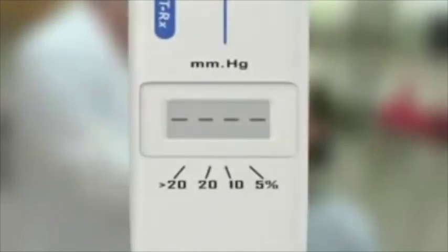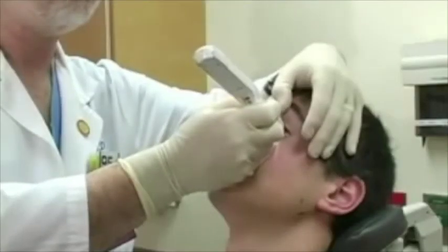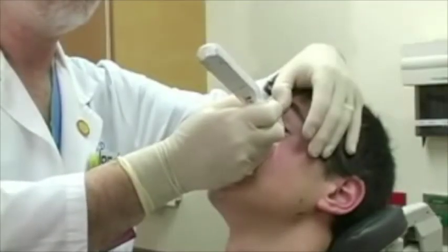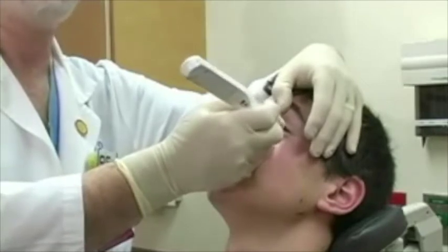A reading above 20% indicates an unreliable measurement and mandates retesting. If four dashes appear on the LCD after the final beep, too few valid readings were obtained. In this situation, reactivate the probe and repeat the measurement. Recalibration is not required.